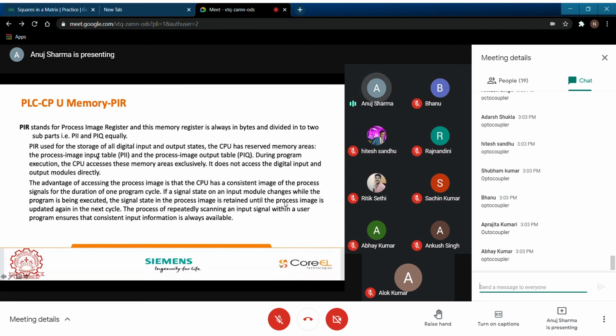Your process image input table and process image output table - PII is used for storage of all digital input and output states. The CPU has reserved memory areas which are PII and PIQ. During program execution, the CPU accesses these memory areas exclusively, and it does not access the digital input and output modules directly.